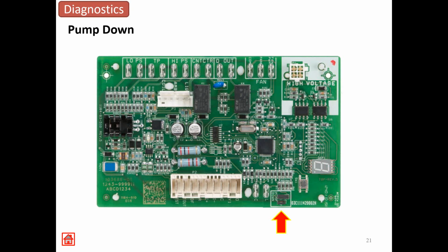This is a tool that I brought up earlier. It's a pump down, and within about 3 to 5 seconds, when you flip the switch, it turns the compressor on, it turns the outdoor fan on, and it ramps them both up to 100%. It also kills the signal to the indoor blower and ensures that it's not running. So it's essentially a pump down, and you would ball off your liquid line. Suction line would continue to be open until you pump the refrigerant down to 20 psi, and then it would stop. So you need to be aware of that with your set of gauges if you're doing a pump down.